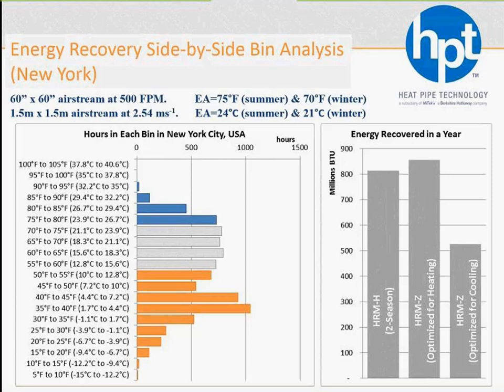Okay, so how does that HRM compare to the other options and all that good stuff? In the two-season recovery, which is level, we actually do pretty good, a little over 800 million BTUs. But if you optimize it for the season with the most BTUs, obviously it's winter in New York, you do even better. But if you optimize it for cooling, you don't do that well. So clearly for this city, optimized for heating is the way to go. And if you really want to do summer-winter recovery, you'll not be far off, but you'll be leaving about 40 million BTUs or so, basically to escape through the exhaust.